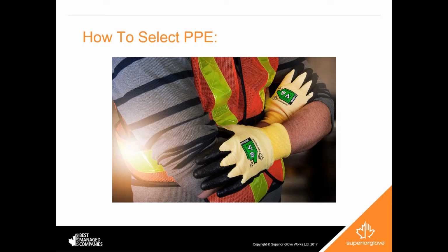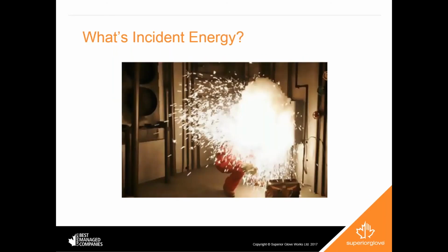So when you tell somebody it's 8 cal or 20 cal or 40 cal, it's obviously going to be much, much hotter than that. So the incident energy is generally measured in testing at a distance of up to 18 inches from the actual arc flash itself. It's called the incident energy because it's energy that isn't supposed to be released. It should be contained. Basically, your ATPV on a piece of PPE means that you have a 50% chance that enough heat will transfer through the PPE to cause the onset of a second-degree burn.